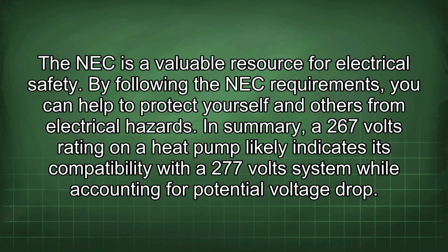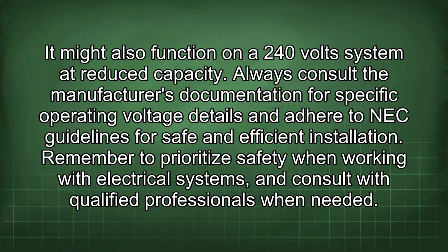In summary, a 267 volts rating on a heat pump likely indicates its compatibility with a 277 volt system while accounting for potential voltage drop. It might also function on a 240 volt system of reduced capacity. Always consult the manufacturer's documentation for specific operating voltage details and adhere to NEC guidelines for safe and efficient installation. Remember to prioritize safety when working with electrical systems and consult with qualified professionals when needed.